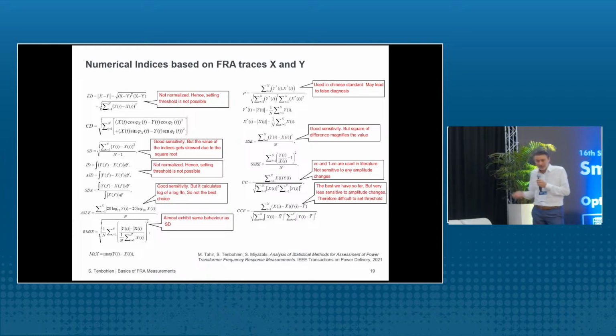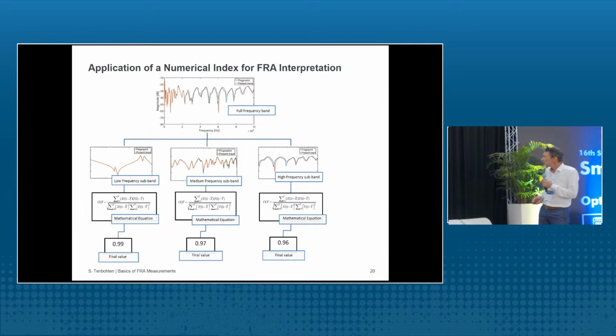And we checked all these formulas. The second point I have to admit: it is never good to apply this formula on the full curve. It's better to look at certain frequency bands. So we check the frequency bands of the core, of the interactions of the winding, and the high frequency band of the windings, and we check what is the index at this frequency.